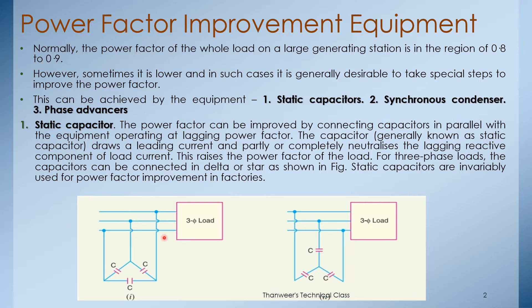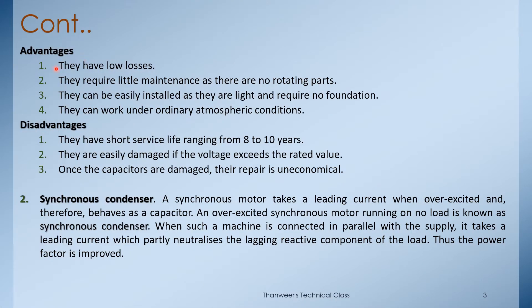The reactive current from the capacitor almost fully neutralizes the lagging reactive component, raising the power factor of the load. For three-phase loads, the capacitors can be connected in delta or star as shown in the figure. Static capacitors are invariably used for power factor improvement in factories.